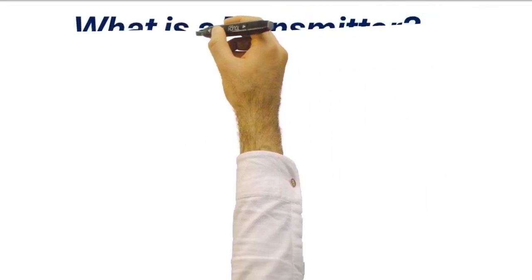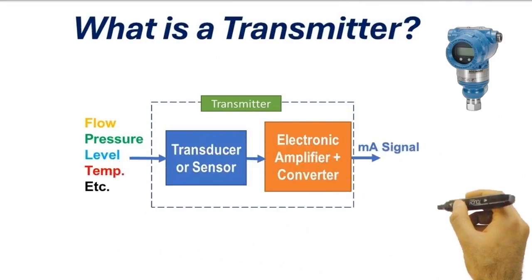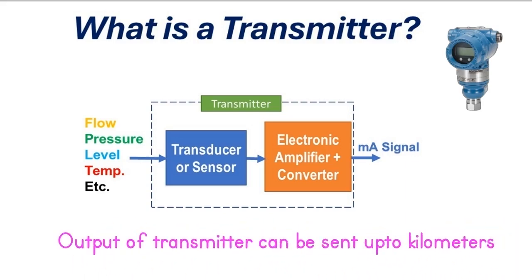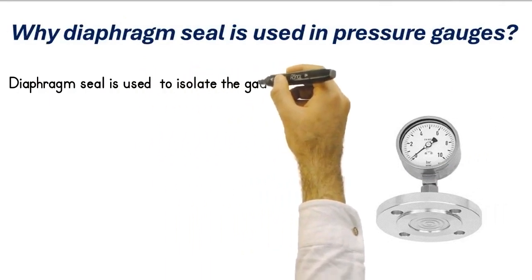What is a transmitter? An instrumentation transmitter is a device that converts the process variable into a standard instrumentation signal, like 4 to 20 milliamperes. The signal produced by the transmitter is proportional to the value of the process variable being measured. This 4 to 20 milliamperes current signal can be transmitted to a control system at a remote location over a two-wire system.